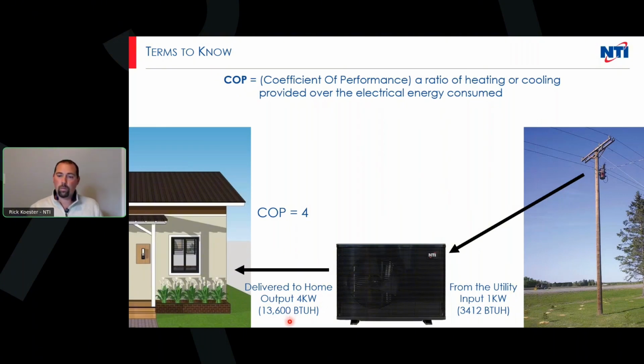So it's BTU delivery, and that's one of the messages I've been trying to drive for a couple of years now: don't focus on the water temp. Obviously, we need to design around a water temp, but it's more about making sure we deliver the BTUs we need to offset the load and make sure that thermostat is satisfied. COP stands for coefficient of performance. A COP of 4 is equal to 400% efficient in an electrical world. I like the dollar approach. It's an easier way to explain it to somebody: if you give me $1 worth of energy or input power, and I give you $4 of energy back, it's a pretty good deal. $4 for every dollar you give me, you'd be pretty happy with that, I would say.